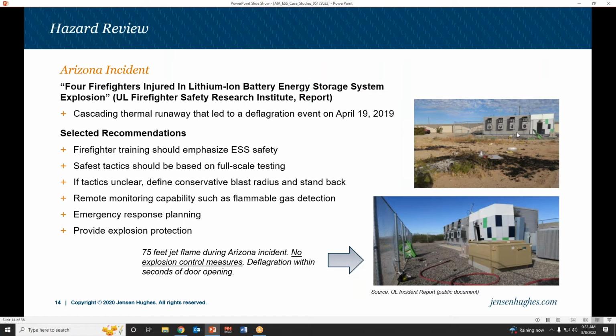And we think, hey, that's a good thing, right? No fire. But thermal runaway continued, and it went through all these modules we looked at, because stuff gets so hot. If one is going, then the one above is going at some point, and then the one above that is going. So more and more batteries went into thermal runaway, and more of those 200-liter releases were being dumped in the room.